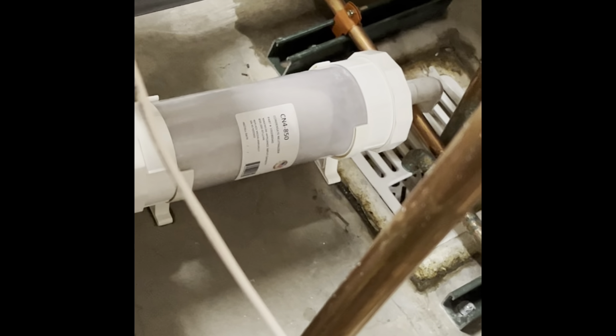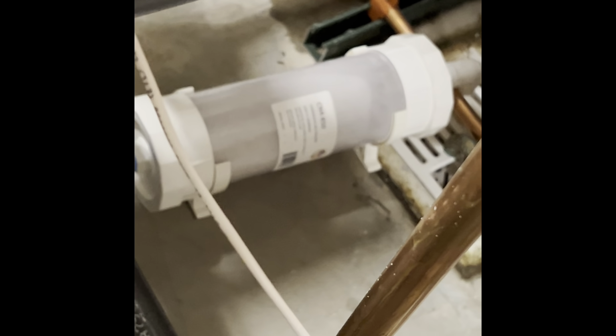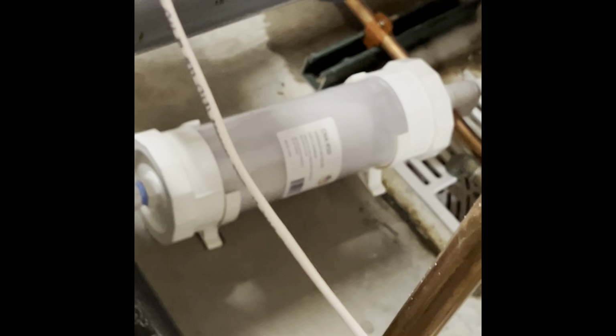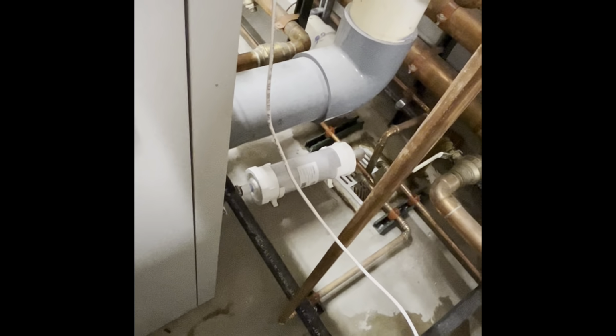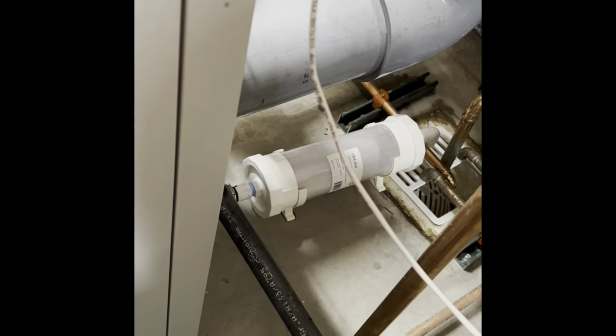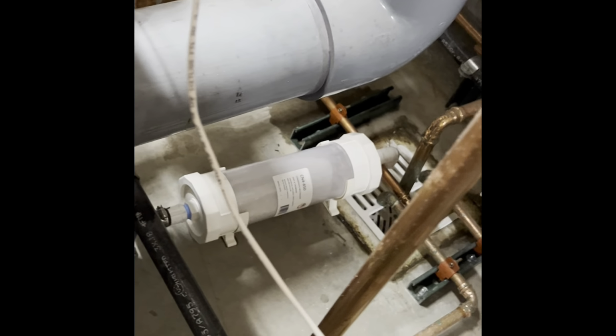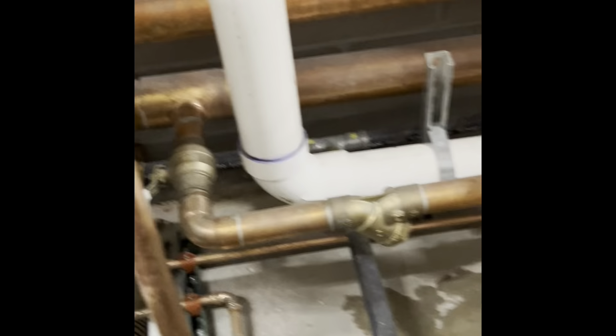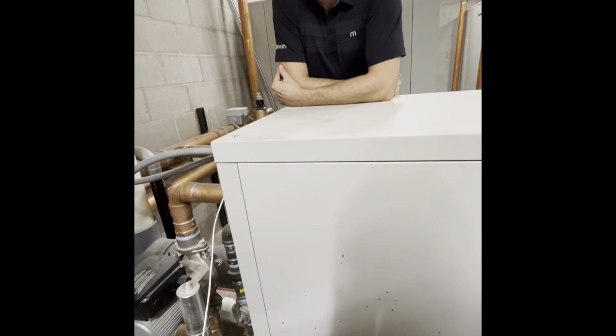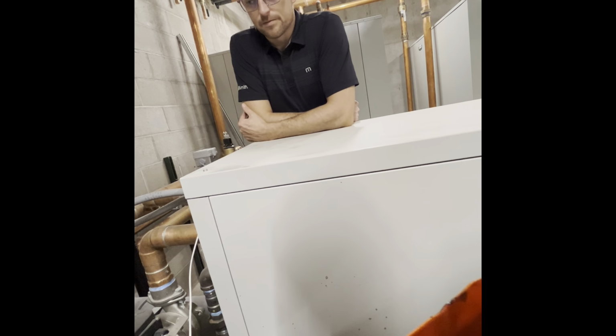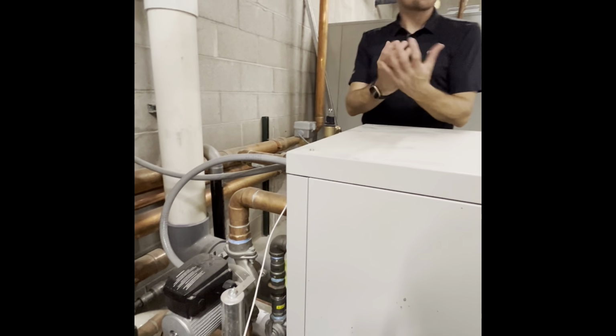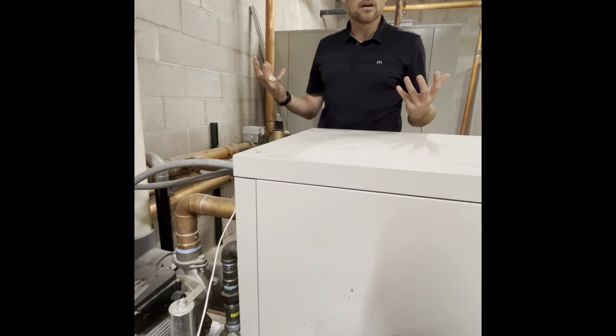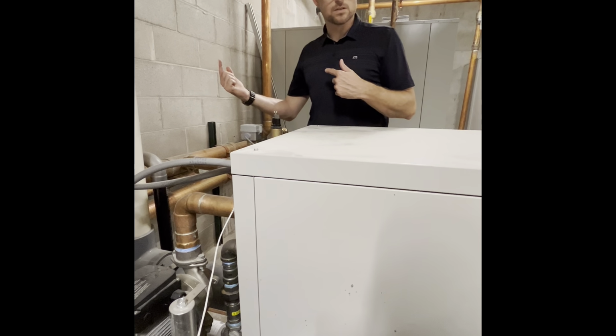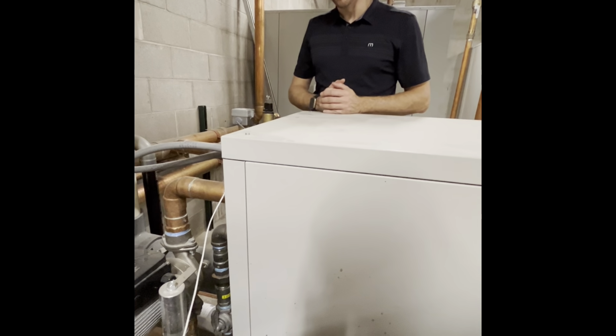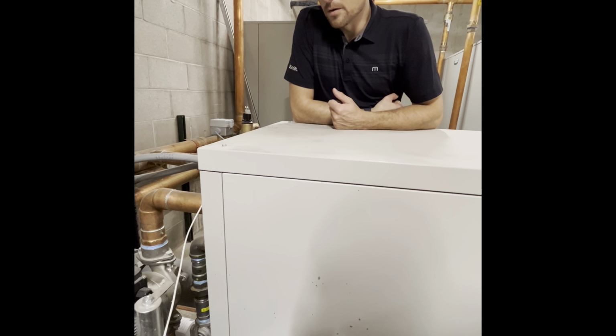And then the white tube, that is the condensate kit. So basically you have a bunch of limestone rocks in there to help neutralize any acidic water, because that condensate fluid is pretty acidic. So that's just going to run off down the drain. That's again something to maintain, easily maintained by, when you're doing your maintenance, having pH strips. That way it allows you to check and see, okay, these are at the end of their life cycle and need a recharge kit, or you could always go to Home Depot and get one of the bags of limestone rock. But the one thing on those, they do have a mesh kind of bag of sorts, so it doesn't allow the rocks to plug up one of the holes, like the exit ports or inlet. But they're relatively inexpensive, and intentionally so.